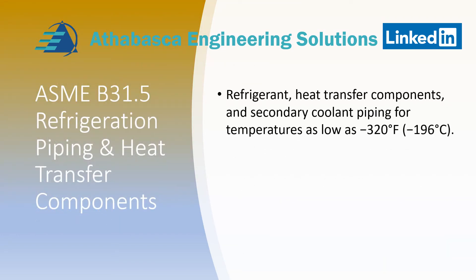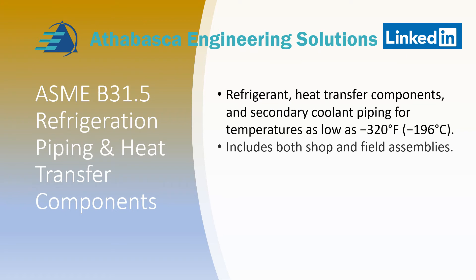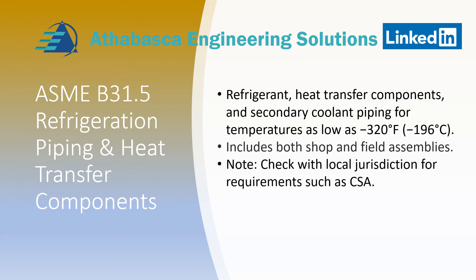We've now completed B31.4 and B31.8 — those are the pipeline specs. We're going to move into service specs. ASME B31.5 covers refrigeration piping and heat transfer components. This specification is mostly used in the United States; CSA is more commonly used in Canada. B31.5 covers refrigeration and heat transfer components and secondary coolant piping for temperatures as low as minus 196 degrees Celsius. It includes shop and field assemblies. Note that you need to check with your local jurisdiction for requirements.